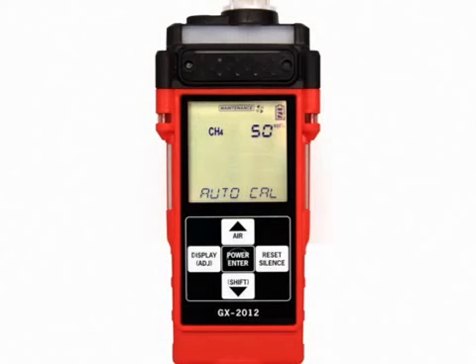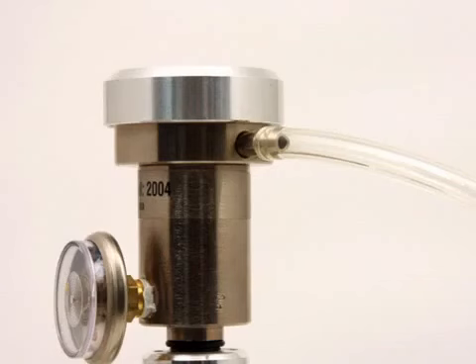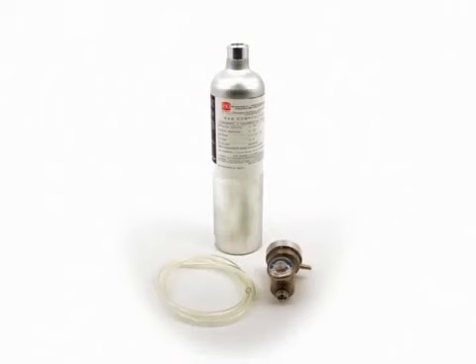If you have a 5-sensor unit and wish to calibrate the percent volume combustible gas sensor, repeat this process selecting the percent volume calibration gas value screen and using a percent volume methane cylinder. Remove the regulator from the calibration gas cylinder. Store the components of the calibration kit in a safe and convenient place.